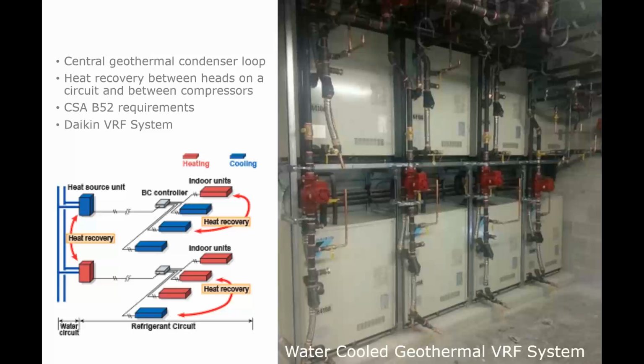The water-cooled geothermal VRF system was the system of choice, very high efficiency. Because we have an array of about 24 units, each with multiple speeds, we get amazing granularity of revving up and down to meet our load, giving great efficiency. We also have the ability to move heat around the building, with the compressors working very lightly to do that—some zones can be heating while others are simultaneously cooling, which is very efficient, especially in our building.